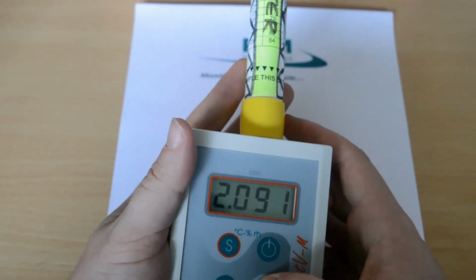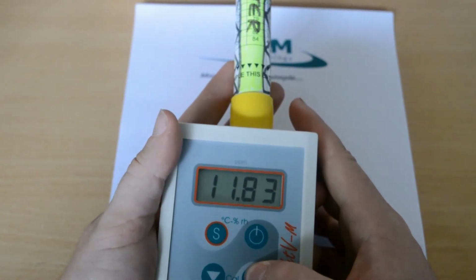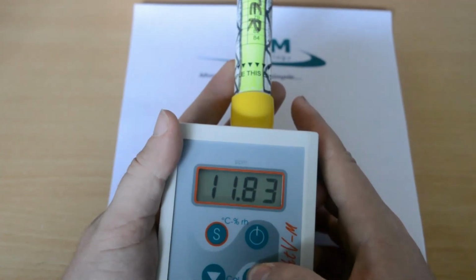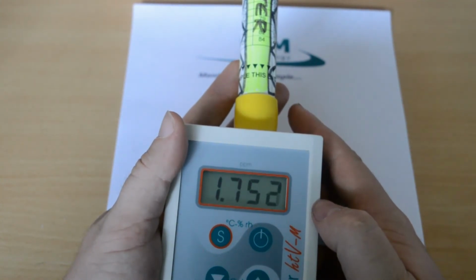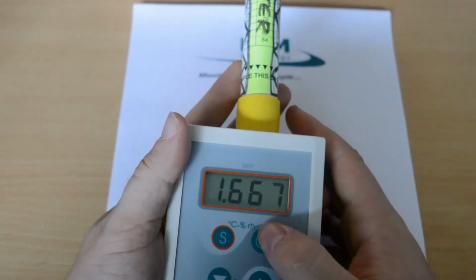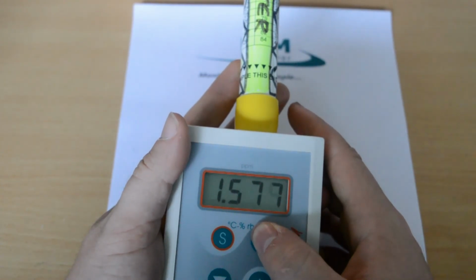If the peak value recorded was less than 5, or the time value recorded was less than 5 seconds, then there may have been a problem with the sampling system or the sensor. Contact PPM Technology or your dealer for further details.